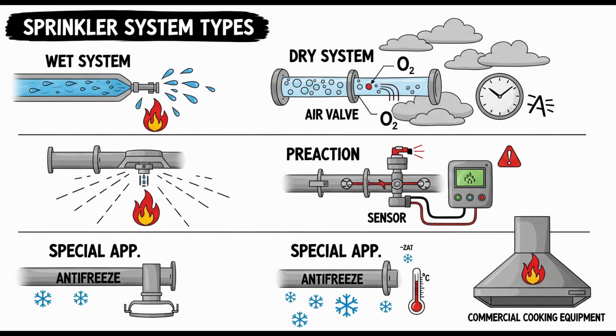Okay. Are there exceptions? Yes. If a compressor serves a single dry pipe system and has a small capacity less than 5.5 cubic feet per minute, then neither an air receiver tank nor an air maintenance device is required for that specific single system. So smaller, dedicated compressors feeding just one system are exempted from needing the extra maintenance equipment.